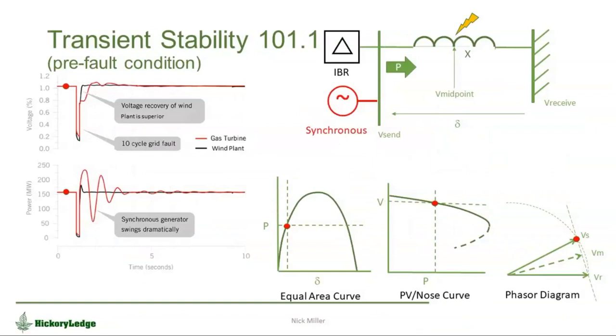So in each one of the following sequence of six or so slides, I'm using the same figure on the left and the red dot. I love doing things color coordinated, and then every once in a while I get abused because people are colorblind. So this slide is all red and green. Sorry for all you colorblind folks out there, but we're looking at the red dot, and across the bottom are these three tools that we are accustomed to using. The equal area criteria tool, which is a classic transient stability tool. The center one is a PV curve, which is the classic tool for evaluating voltage stability. And then on the far right is the power transfer phasor diagram, where the angular separation of the sending end voltage and the receiving end voltage and the midpoint voltage look very familiar, driving home the emphasis that midpoint voltage is on a straight line, not on the arc, the constant voltage arc of the drawing. So everybody knows this stuff.